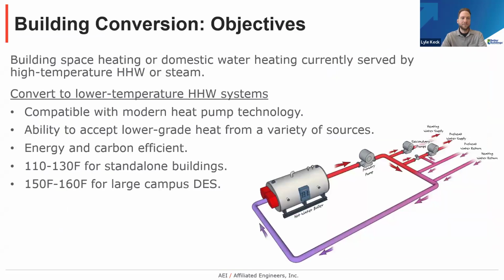Next slide, please. So the objective, talking first about building conversions, is that you need to ensure that the zone level and the building level HVAC heating devices are compatible with the new low temperature heating hot water systems. In some cases, a VRF or a package solution might fit the application, but today we're really going to talk about the very common challenge in large commercial buildings of transitioning to a lower temperature heating hot water system for electrification and decarbonization purposes. And some of the objectives are shown here.